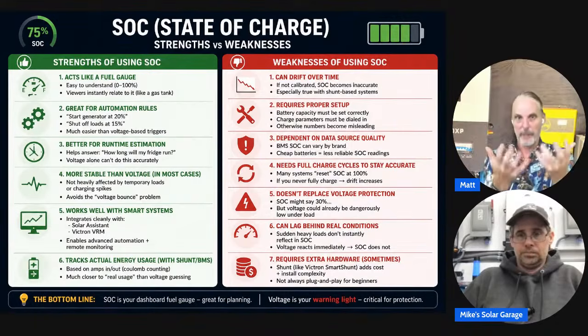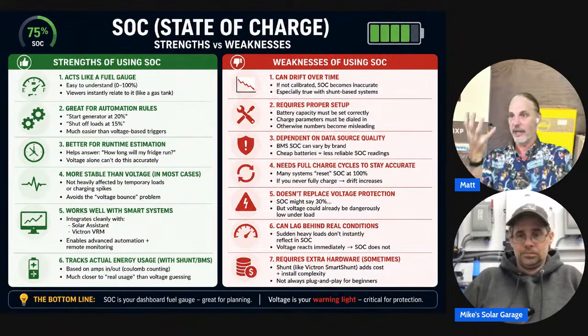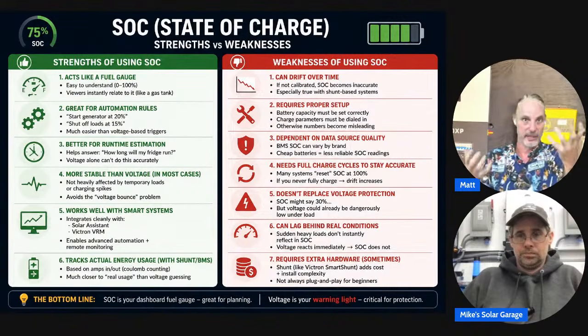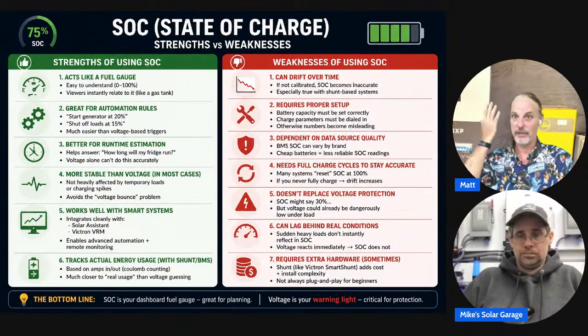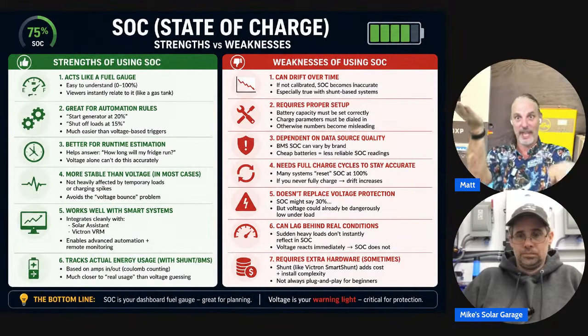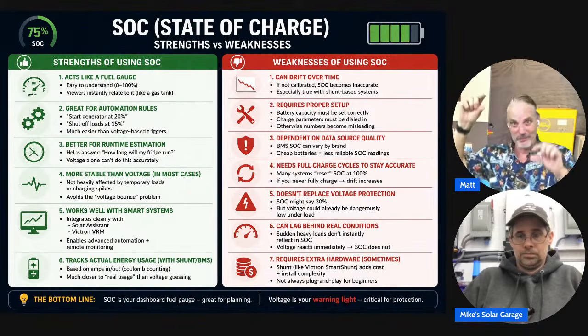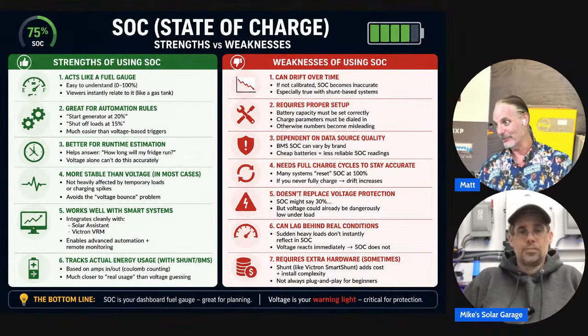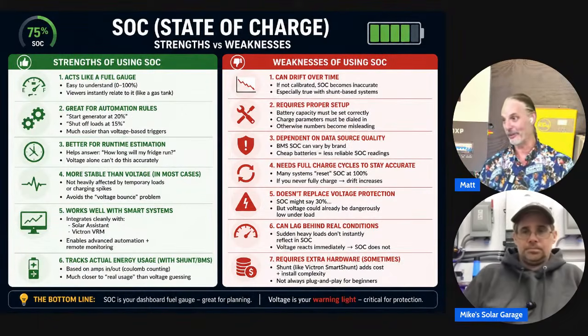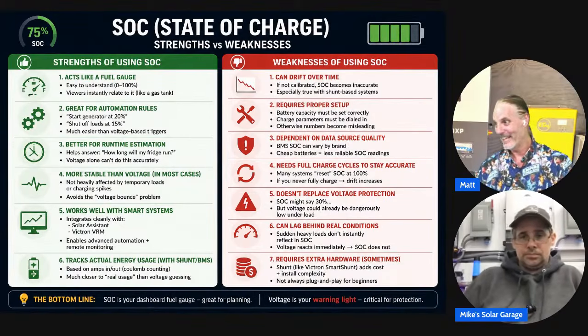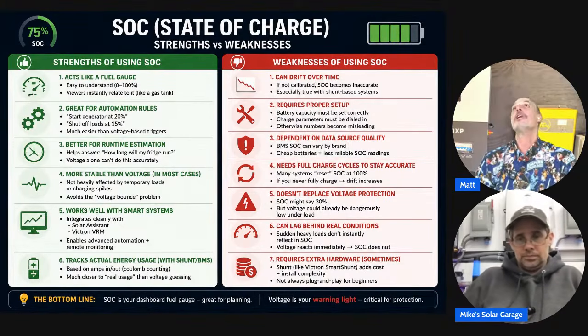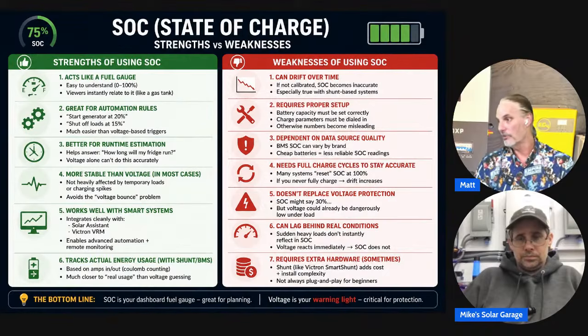But when you separate them into 2 separate units, they have no awareness of each other and can't adjust for each other. When one's state of charge says 0, it shuts off, and when the other's says 100, it shuts off. That means as the gap grows, your window of usage becomes really small sometimes—usually not to the extreme of 100% like this one, but he'd had it hooked up for years, and who knows, it could have been like that for the last year.